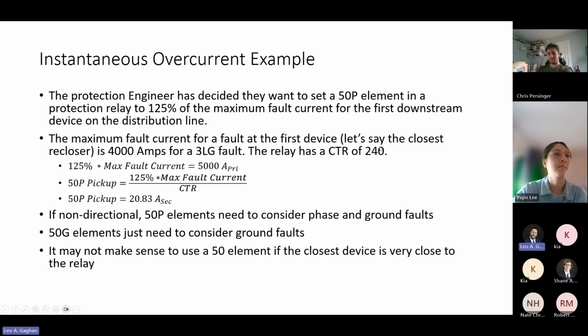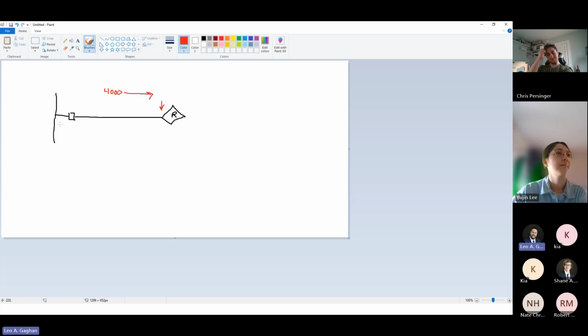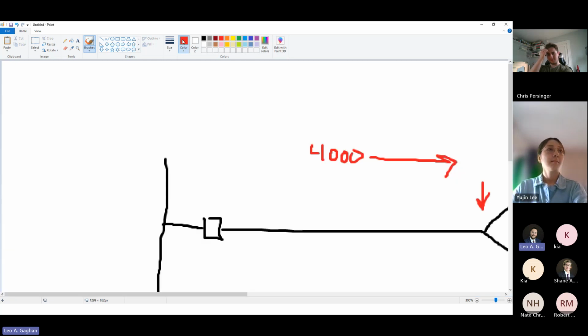And then, as always, the relay is based on the information that it has. So there's a CTR of 240. So our setting would be that 125%, 4,000 over the CTR of 240, which gets us 20.83. That would be the setting that we put into the relay. And we have to take that CTR into account, just because those 4,000 amps, that's a lot of energy. That would blow any electronics to shreds, really.